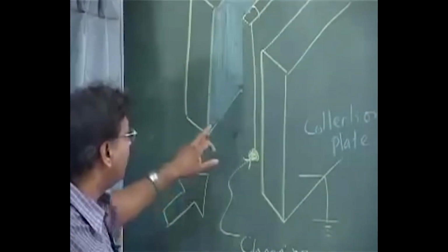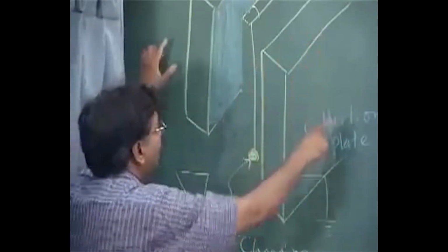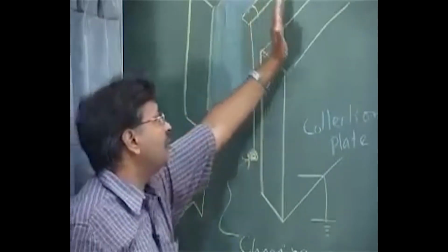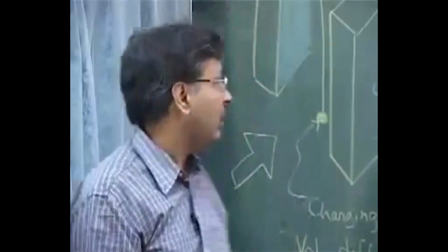So then what they do is, once this is there, for every field, this plate and the charging electrodes in between, this thing is called one field. It's very common to have 5 fields, 6 fields, 4 fields to remove the particles, because in the successive thing we will see that one.